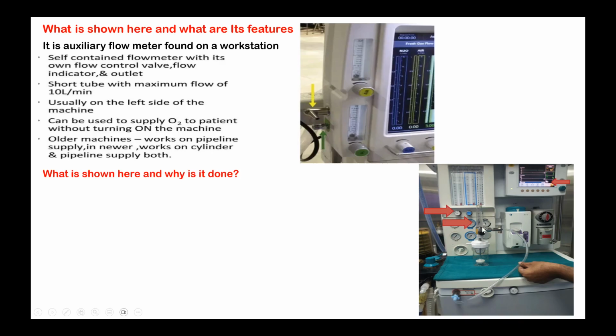For those who are not able to clearly see, a flow meter which you see in the wall outlet for delivering oxygen is connected to the common gas outlet through an adapter and a tubing. What is the purpose of this? And you can see the oxygen knob is kept closed. The floats are not flowing up. But the bobbin or the float in the flow meter tube is going up. Then what does it indicate? Oxygen supply failure. There's a leak.